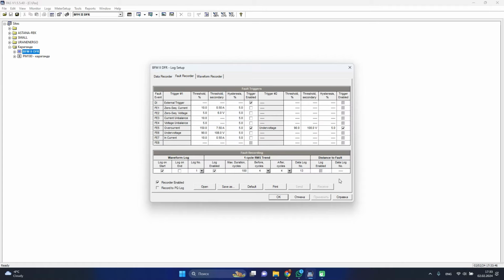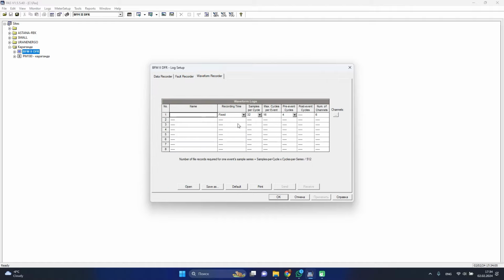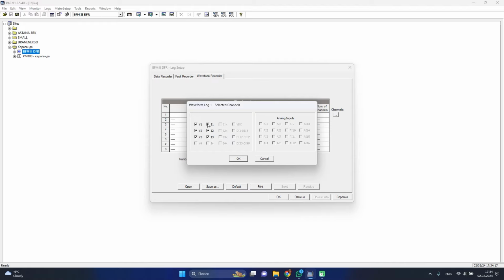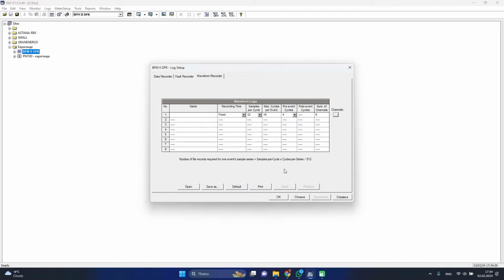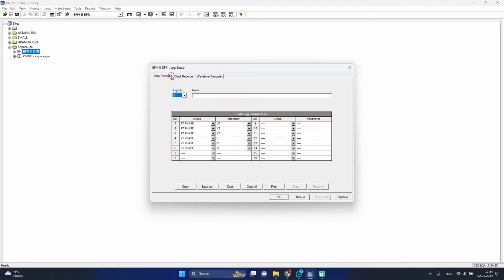And the main difference between the BFM II and BFM II DFR is that in the DFR we have the fault recorder, where in this menu we can change some fault recording setups, where we need to save it, and we need to have the recorder enabled. We can change the setups for the waveform recorder, for the samples and cycles, and to define the fault we need to select all the channels, all the voltages and currents.